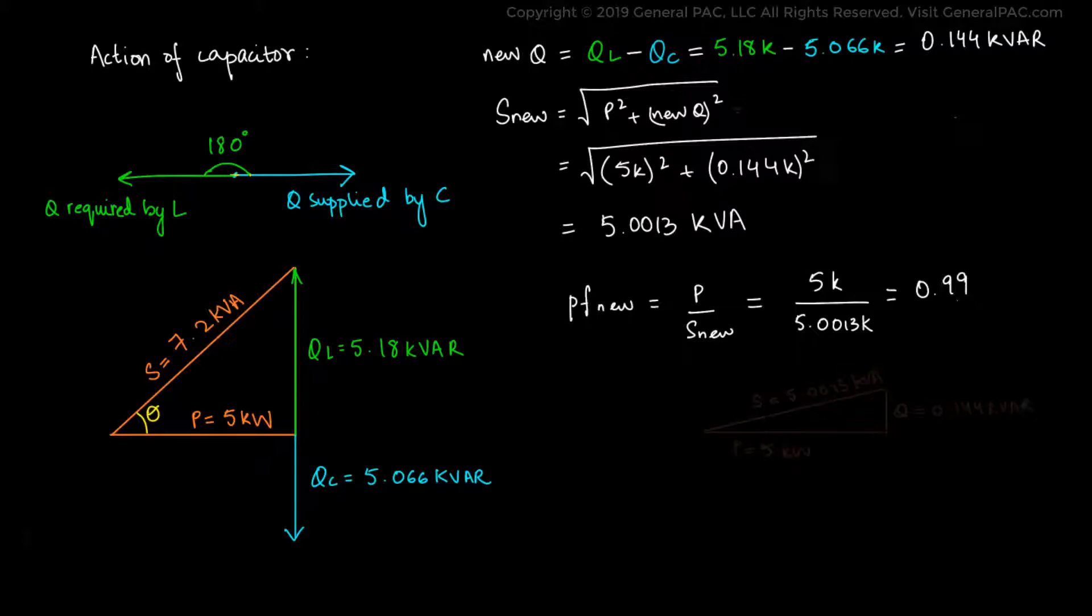We can redraw the power factor triangle to visualize the effect. And you can see that the true power and the apparent power are close to each other, but not quite 100%. And there's still some reactive power that's left over. The phase angle between the apparent and the true power now comes out to be 8.1 degrees, which is a massive reduction from the original phase angle of 46 degrees.